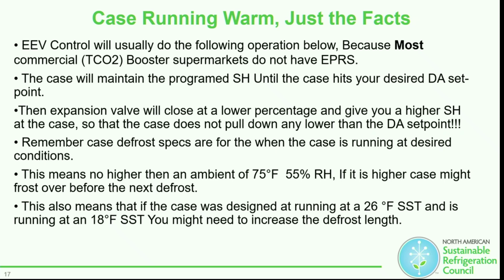The case will maintain the programmed superheat until the case hits the desired discharge air set point, and then basically either shut off entirely or shut off to a minimum percentage to keep flow throughout that coil. Depends on who programmed it. The expansion valve will close to a lower percentage to give you a higher superheat at the case, so that the case does not pull down any lower than the discharge air set point.